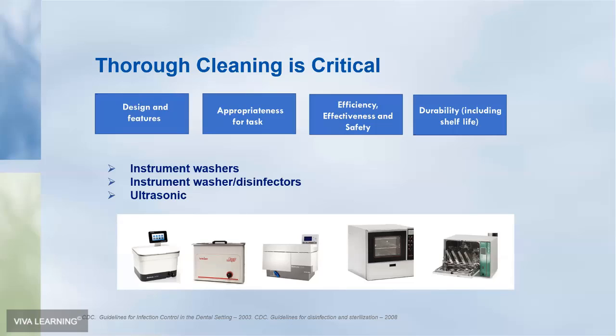So let's look at cleaning. We talked earlier about alcohol-based hand rubs not being able to remove soil. Well, if you leave soil on instruments, the sterilant, typically steam in our case, in autoclaves, cannot penetrate the soil. So it compromises the ability to sterilize those instruments. So cleaning is an absolutely critical step.